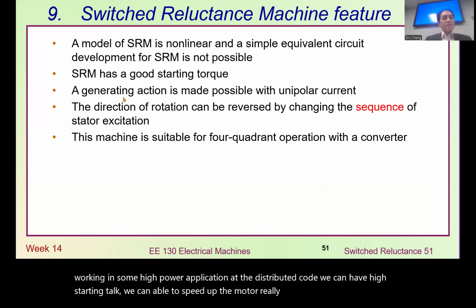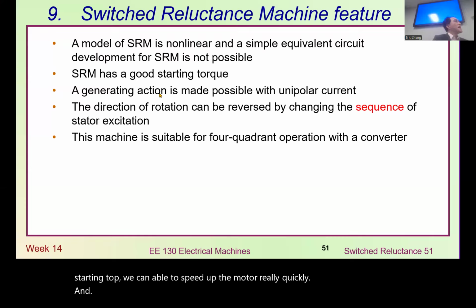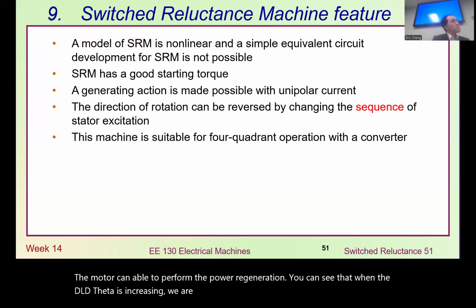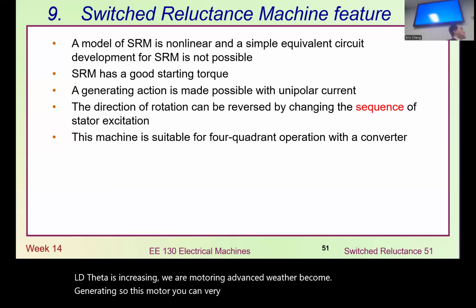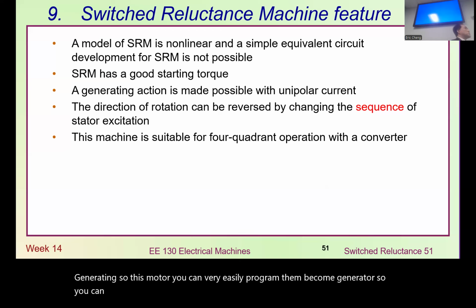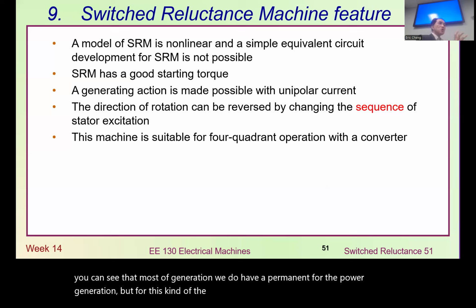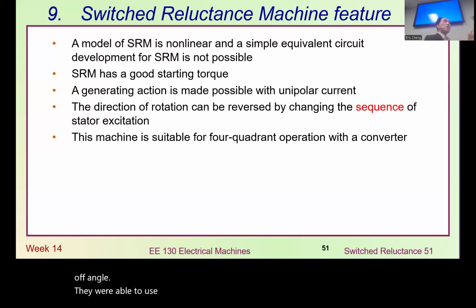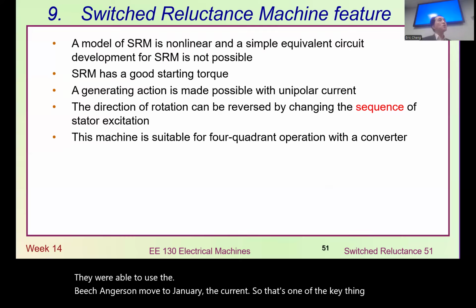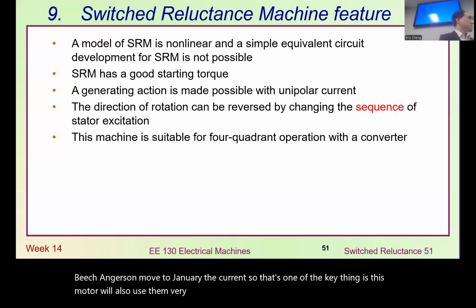The motor can also perform power regeneration. When the dL/dθ is increasing we are motoring, and vice versa we become generating, so this motor can very easily be programmed to become a generator. Most generators require a permanent magnet for power generation, but for this motor we can just control the turn-on and turn-off angle, then use the regeneration mode to generate current. So this motor is also often used in power generation.